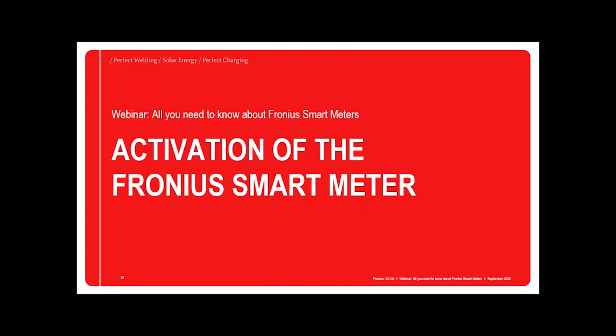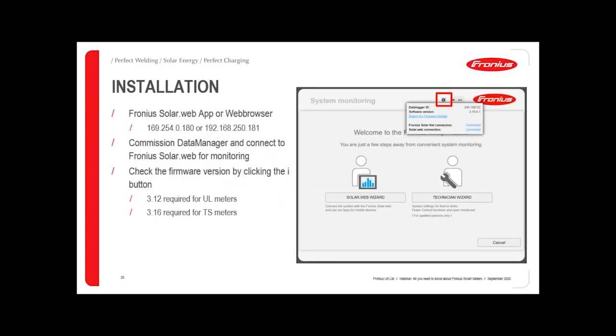So we've just seen how to install the wiring and how to check the CTs. What we'll look at now is how to activate the smart meter using our data manager and the online web browser interface. We'll assume that we've already gone through the connection to SolarWeb, so we've set up the inverters and we've got the system online. What we need to do is then go to our technician wizard — there's a step-by-step process for detecting the meter and setting export limitation if required. We should always check the firmware version of the data manager. If you click on the little information tab, you'll see the current software version. For the UL meters, we need to have version 3.12, and for the new TS meters, we need to be up to 3.16. If you have an older firmware version, you can just click to search for the new firmware and update that over the internet.